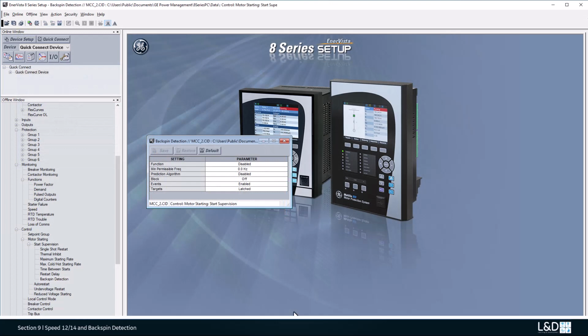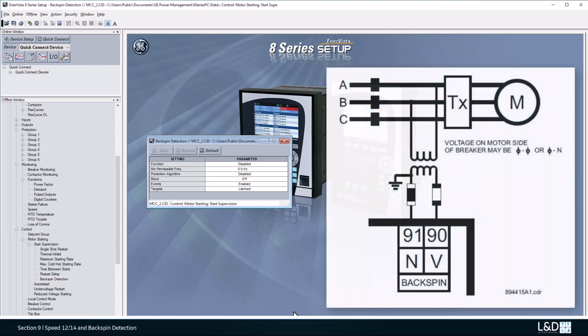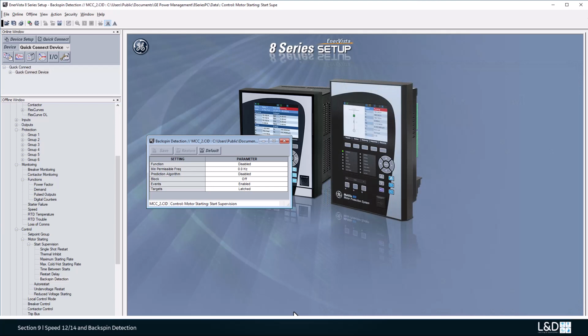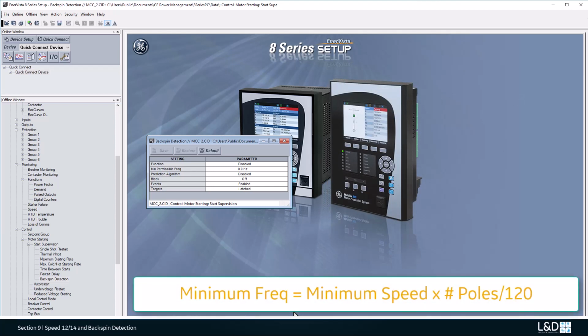The backspin detector enables 859 to detect motor freewheeling in reverse in downhole pump application. The backspin detection allows 859 to sense if the motor is spinning after the primary power is removed. These inputs must be supplied by a separate VT mounted downstream on the motor side of the breaker or the contactor. The calculation of minimum frequency equals the minimum speed multiplied by the number of poles divided by 120.